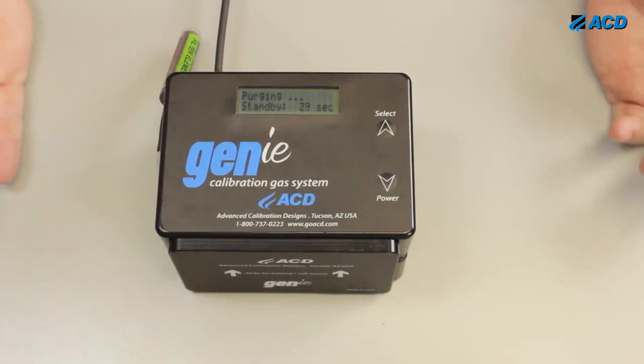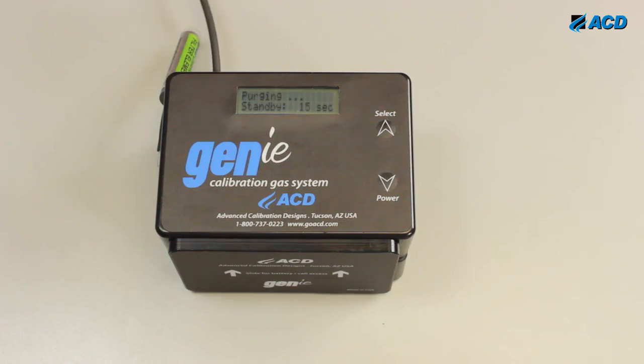Now it purges. The purge cycle is just to get any of the corrosive gas out of there. This is chlorine. Our other gases, H2S, HCN, hydrogen, all these gases, you want them purged out of the system. So it will automatically shut itself off. You don't have to wait for it. Once you've got to the purge cycle, it's going to shut itself off.